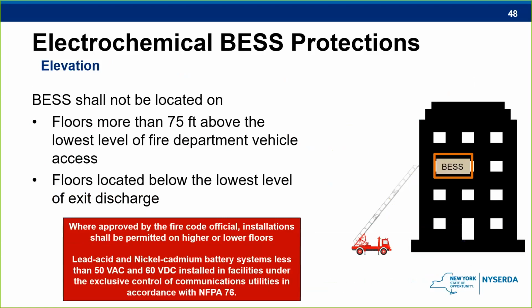So generally speaking, you want the fire department to have easy access to respond to an incident. Therefore, these systems cannot be located more than 75 feet above the access point or below the lowest exit floor. However, like many other requirements, fire department officials have the right to permit higher or lower, but only if they feel comfortable with the safety features and the fire protection systems that were installed. It's also important to note on this slide that rooftops are treated a bit differently and they have their own set of requirements, and we will go through those in a little bit.